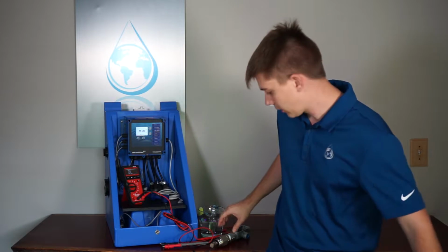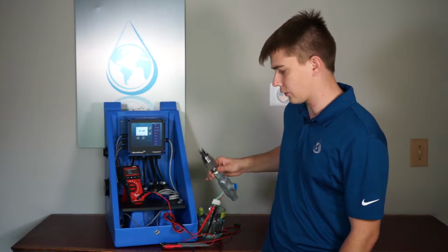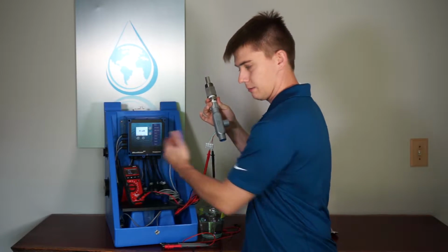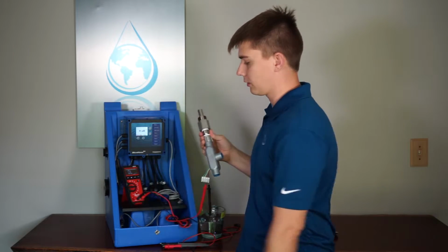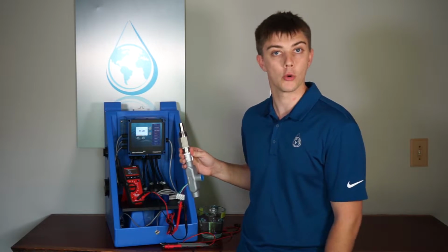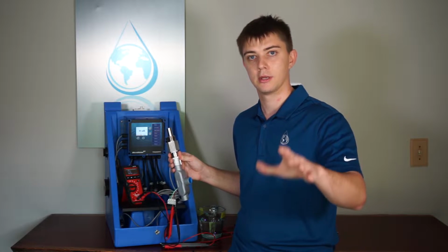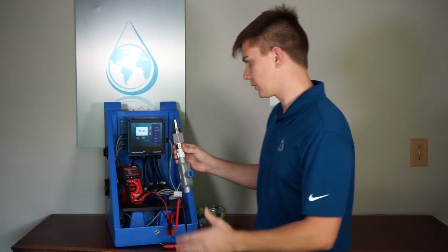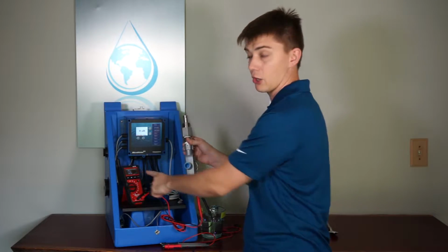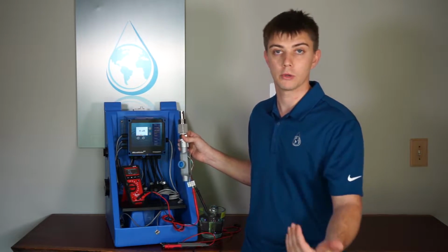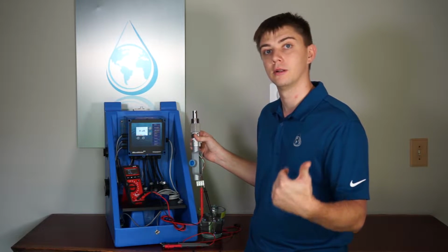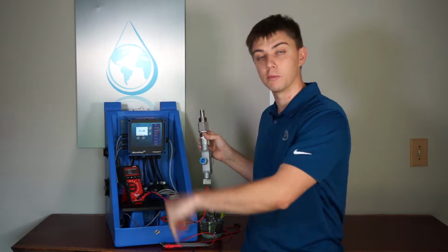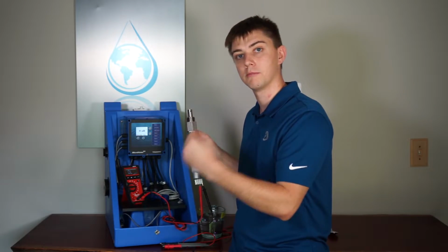water. So here I have just a standard boiler probe, and all I've done is wire this boiler probe up to a multimeter. Now the multimeter is going to show me units in ohms, not microsiemens, but they're inversely proportional. Very, very similar. So if I have this in air, it's showing me an open loop, which would be really pure, low conductivity. It's infinity here, but it would be zero in microsiemens.